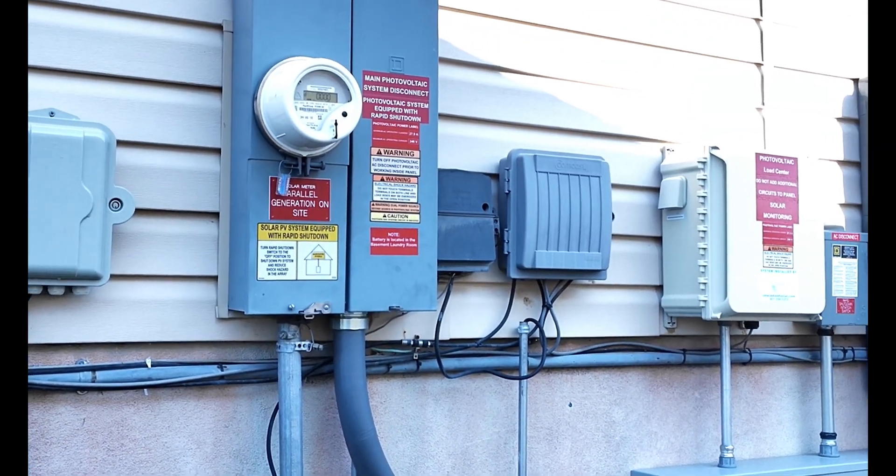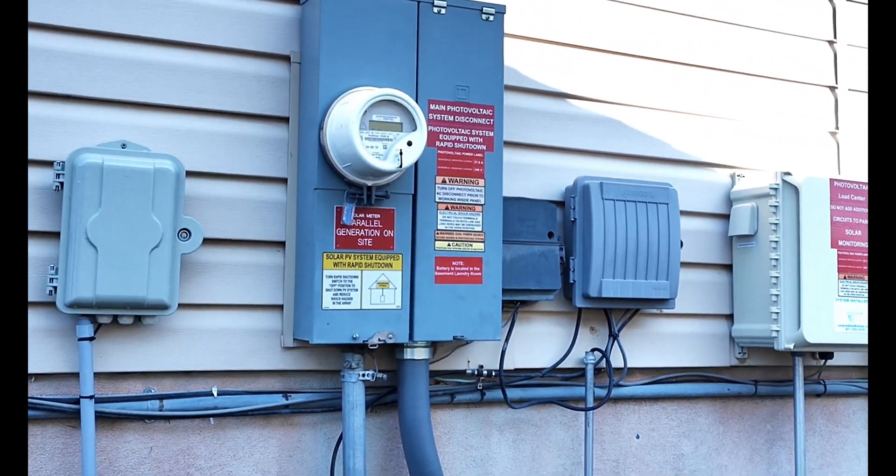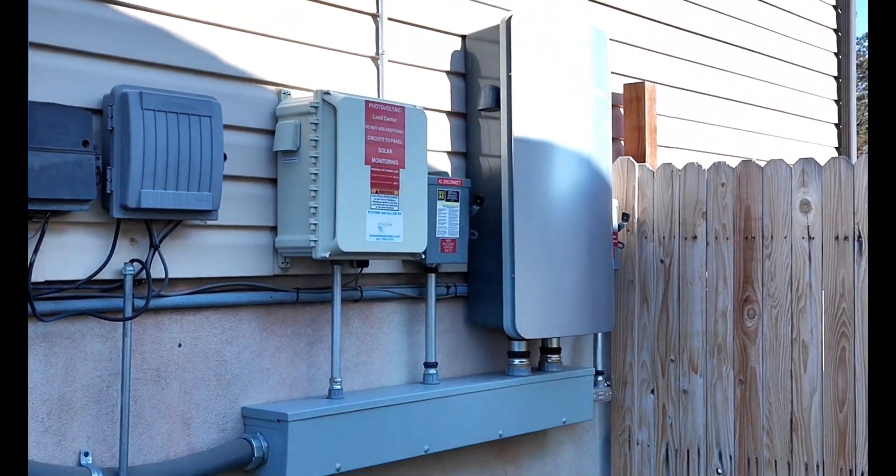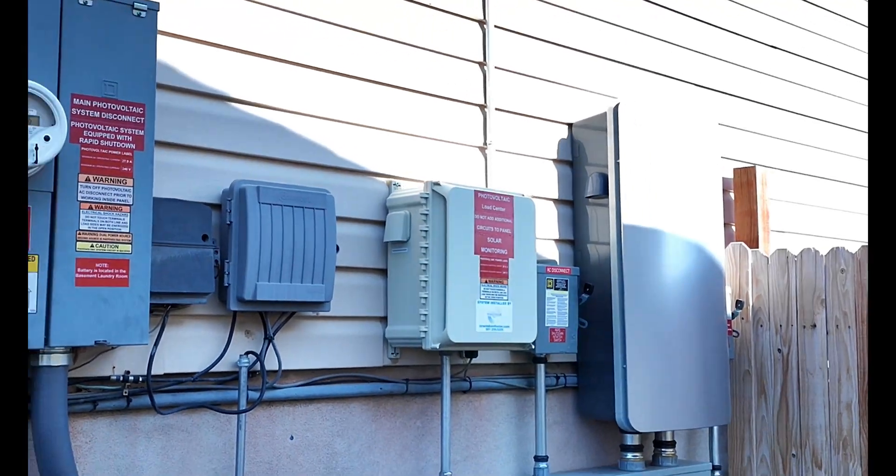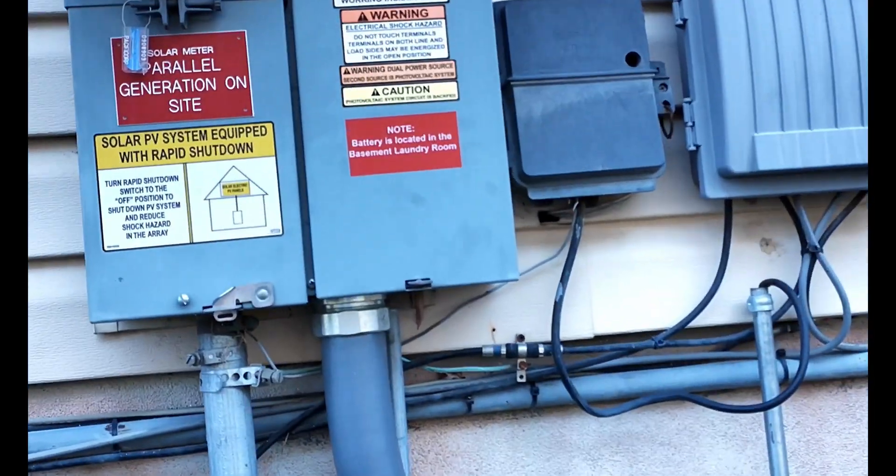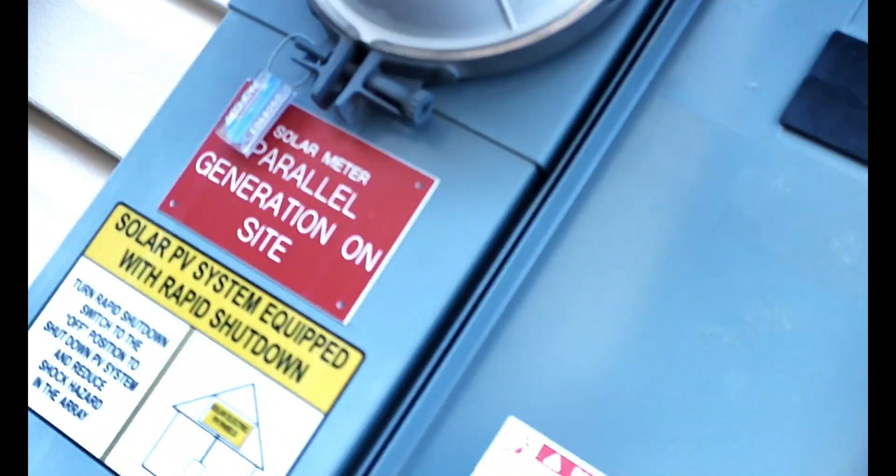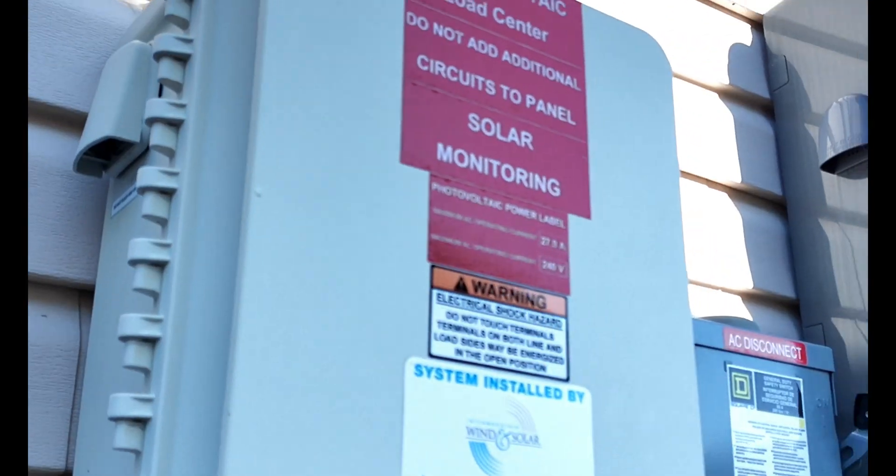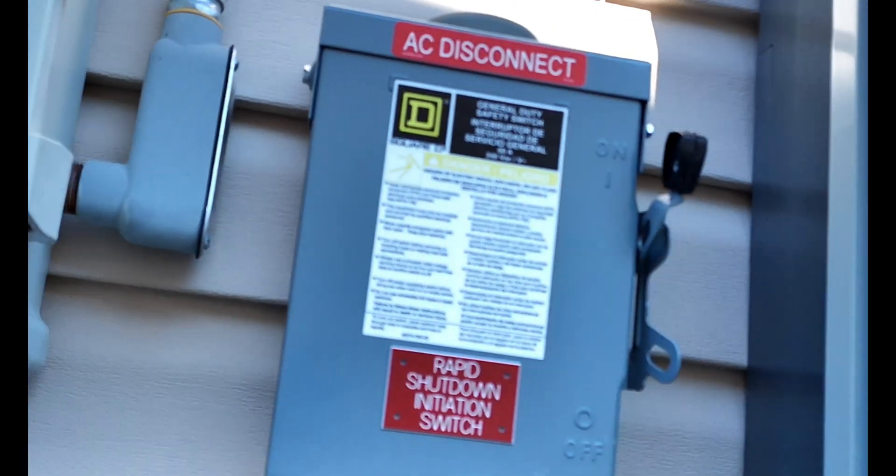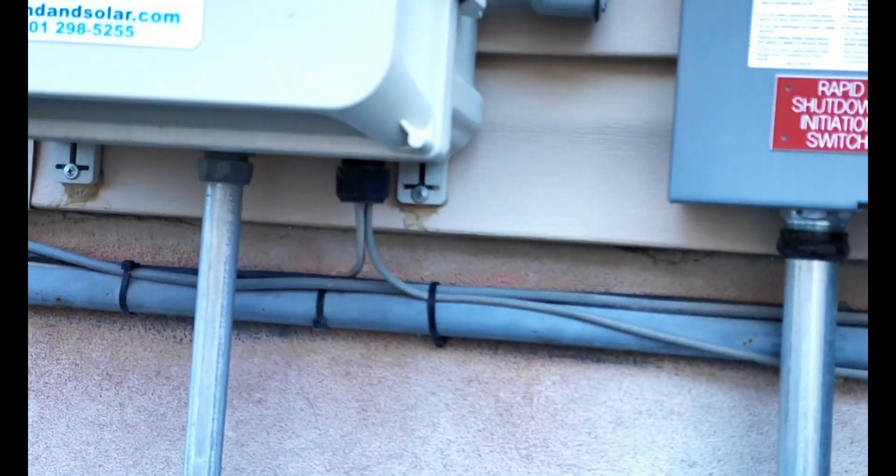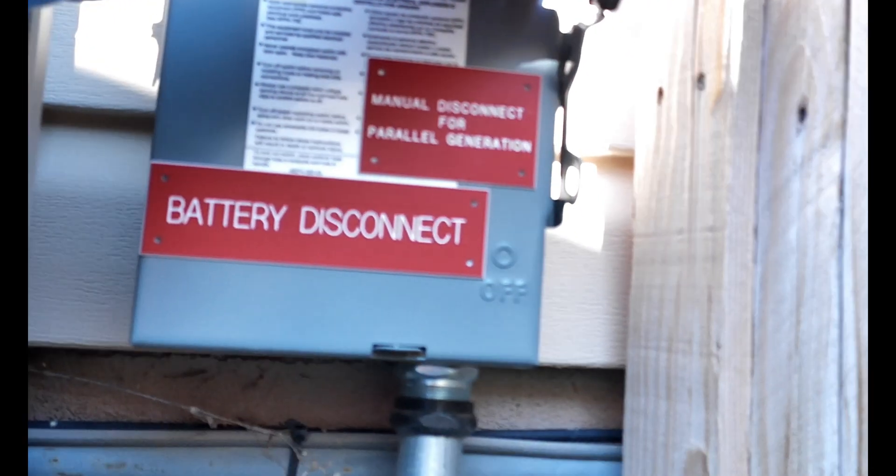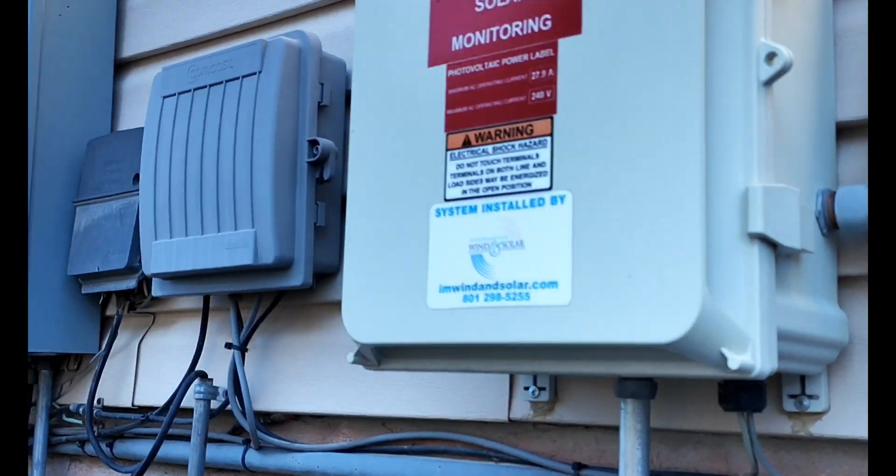So out here we've got our main panel—our net meter for our solar. These are all our transfer switches for when the power goes out. First thing we need to do is cut off the power to the house, which is here. There's our main breaker, our 100 amp. Solar just kicked in. We want to completely shut down the AC—that's the rapid shutdown. And then we're going to shut down the battery disconnect. Now everything should be off. We'll go inside and check our line to make sure they're not hot.